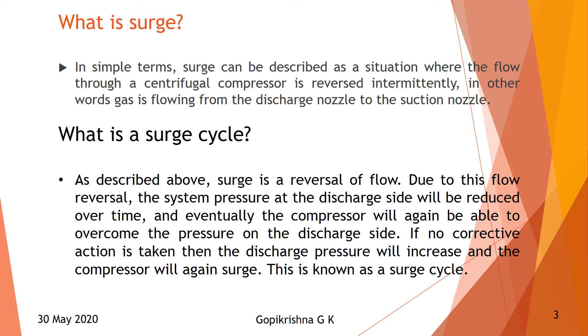Due to this flow reversal, the system pressure at the discharge will be reduced over time. Eventually the compressor will again be able to overcome the pressure at the discharge side. If no corrective action is taken, the discharge pressure will increase and the compressor will again surge. This repeating cycle is called a surge.